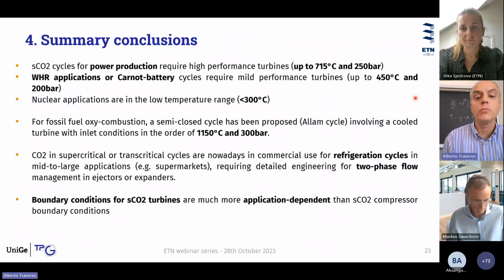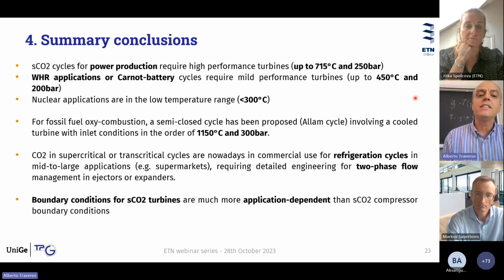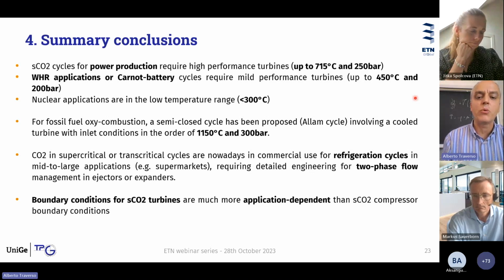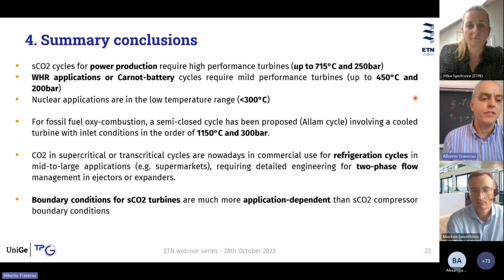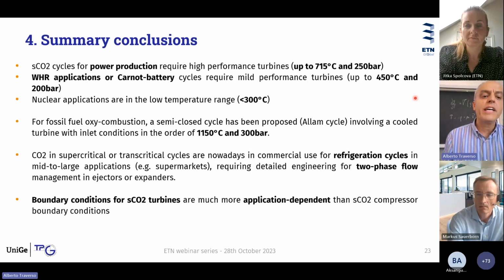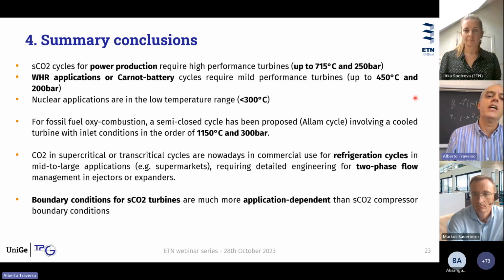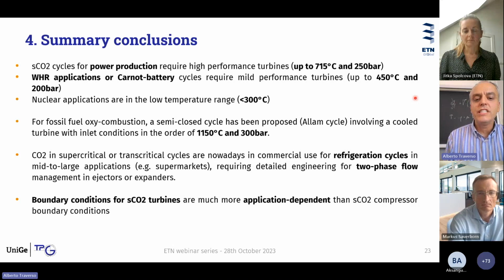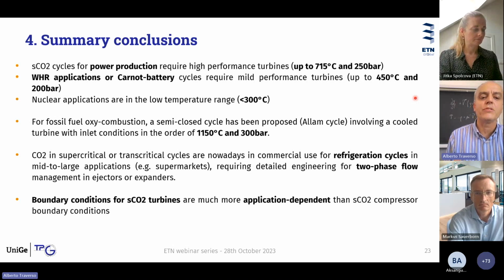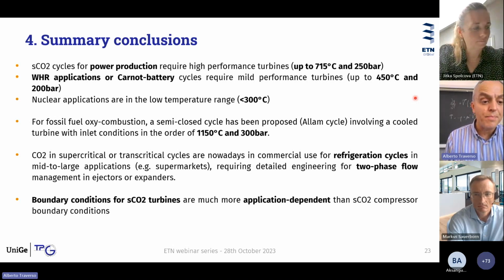We have seen up to more than 700 degrees C and more than 200 bar. For waste heat recovery application or Carnot battery, we have seen that milder performance turbines are required, in this case maximum 450 degrees C and 200 bar. Nuclear applications are in the lower temperature range, below 300 degrees C, but of course safety there is a more relevant issue. For the outlier turbine, we have seen that fossil fuel oxy-combustion, such as in the Allam cycle, can require very demanding conditions, such as more than 1100 degrees C and 300 bar.